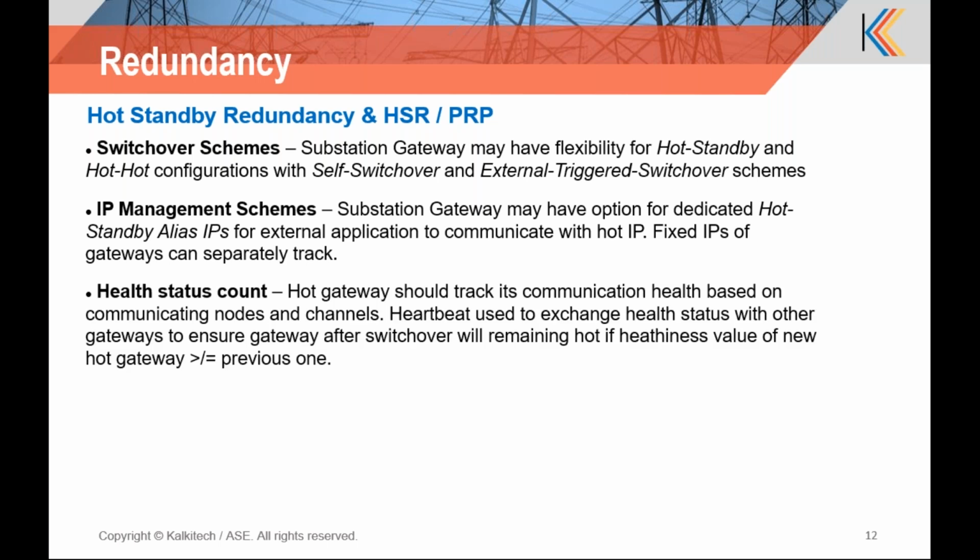Then the health status count. There is a dedicated link between the hot and standby gateway, and a heartbeat is always exchanged between both gateways. The health status count is calculated intelligently depending upon the number of nodes online and the number of channels working, and this health status count is always transferred to the standby gateway.